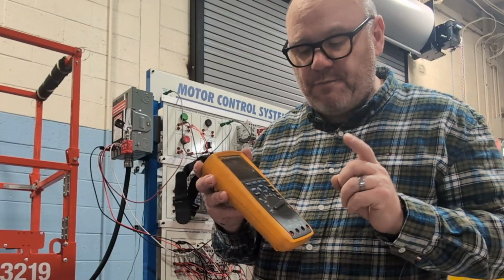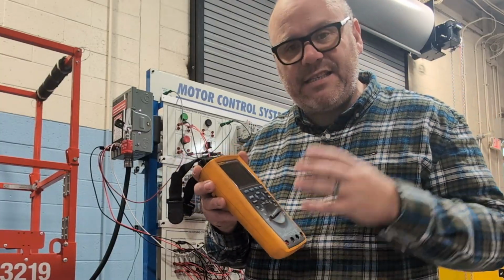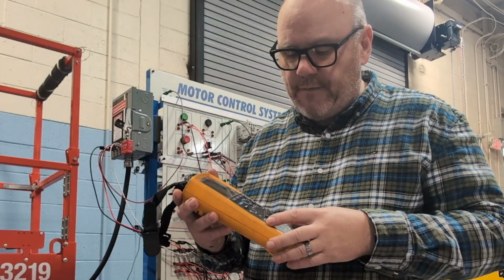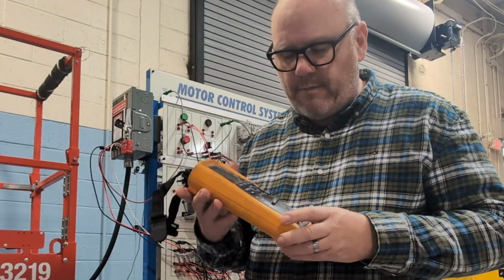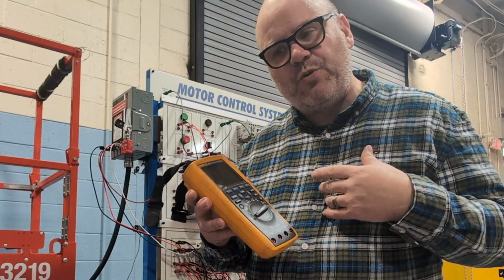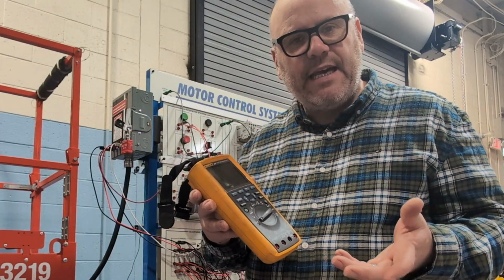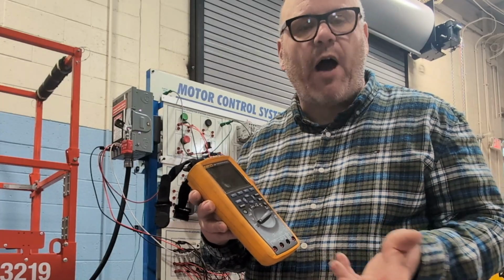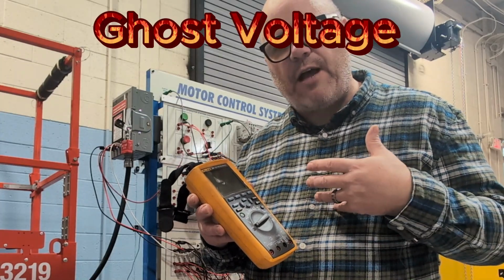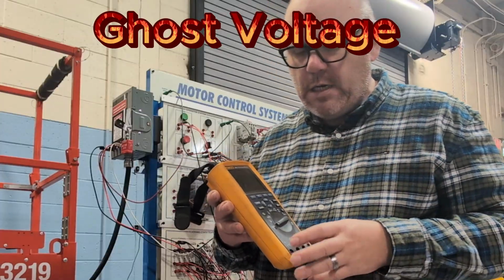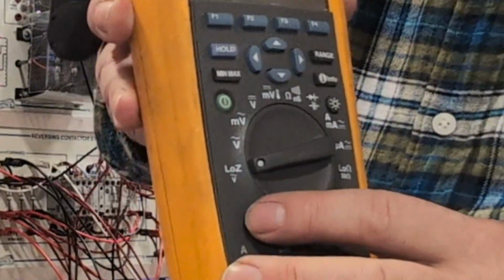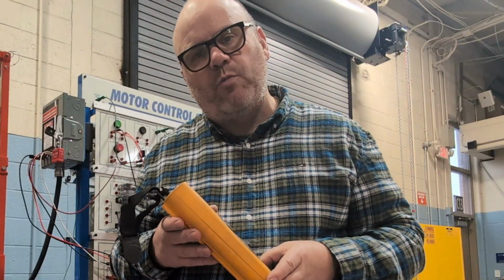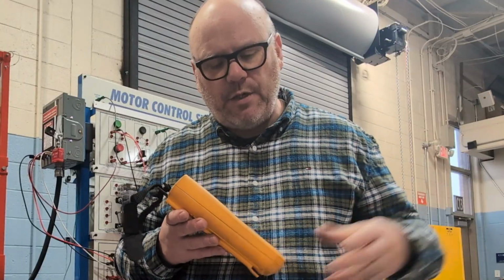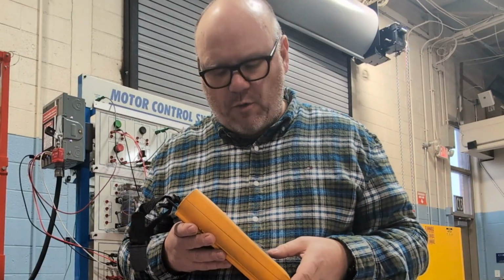With two things that helped me and saved my butt: regular meters don't have low impedance. Low impedance helps you find true resistance in a circuit that's close to something like an electrical drive, because the drive supplies a false signal to the wire. So there's low LZ volts, low LZ ohms. When I was testing it, it was giving me 1,000,000 ohms when the drive was running, and when it was off it would go down to 29 ohms. When I got the right meter, no problem.